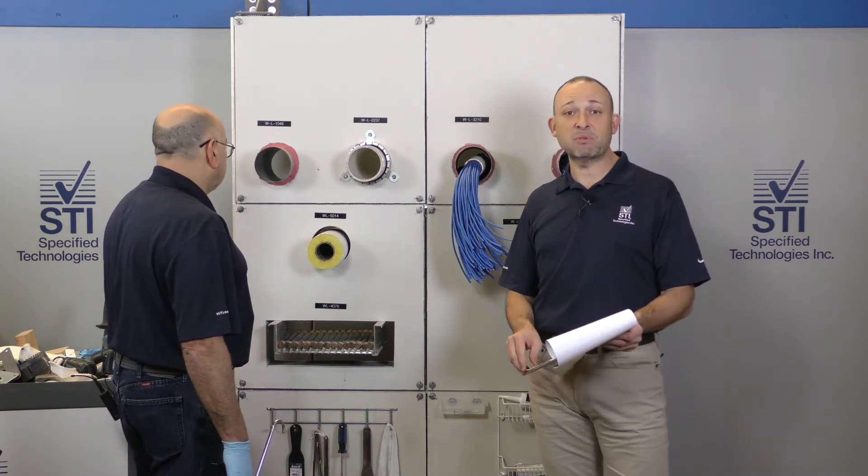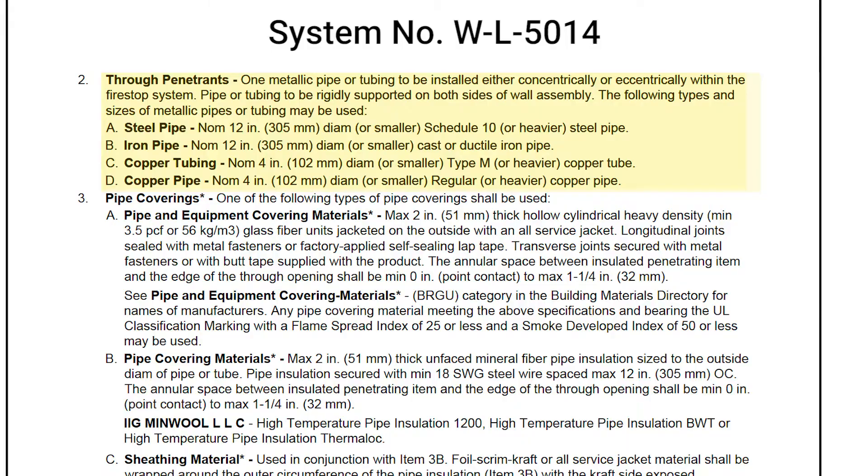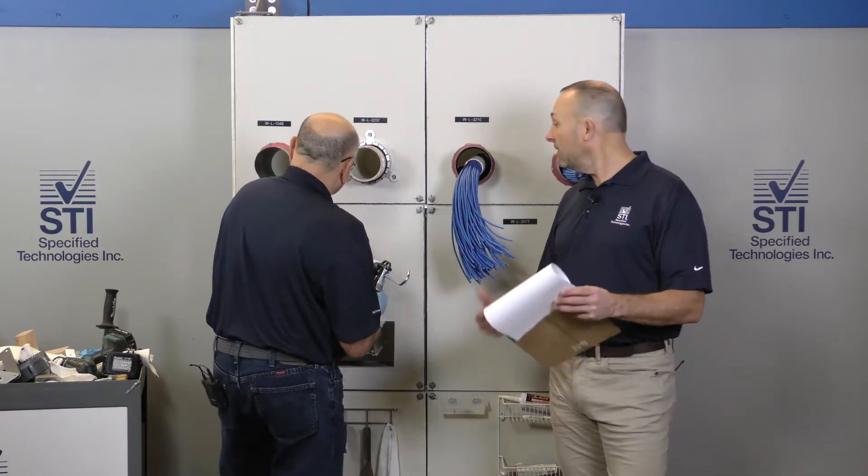This system gives us that optional steel sleeve, which we don't have in this case. We'll take a look at the through penetrants, steel pipe up to 12 inches, iron pipe up to 12 inches. Always check those maximums within that system.